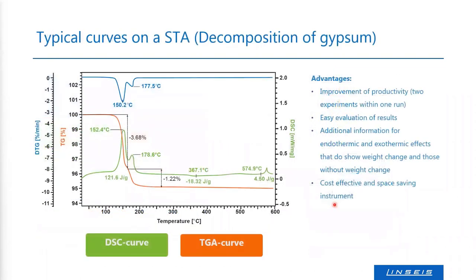Typical curves from an STA instrument look like this. The red curve gives the mass signal — here for a gypsum sample undergoing decomposition — showing weight loss in several steps. You can analyze the weight loss and also measure, with the DSC signal, the enthalpy involved in the decomposition processes.